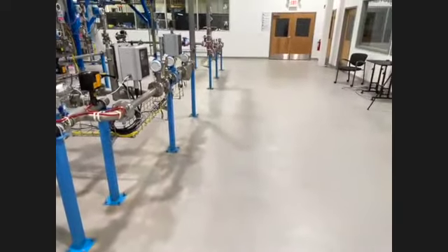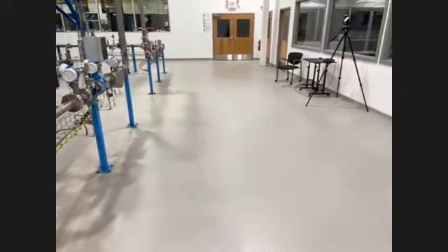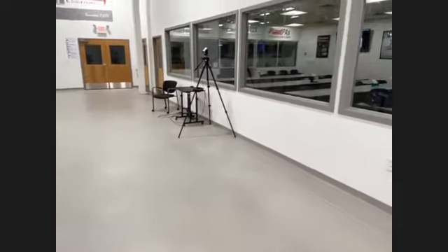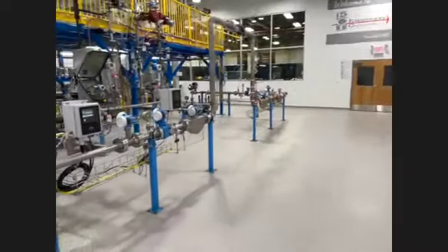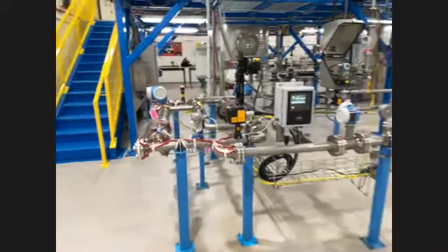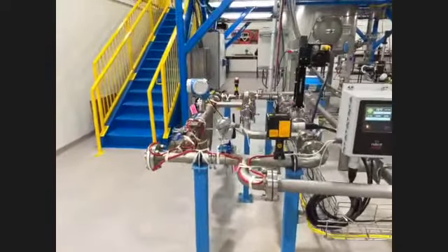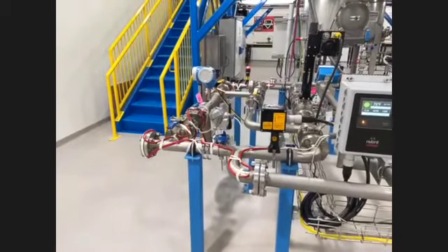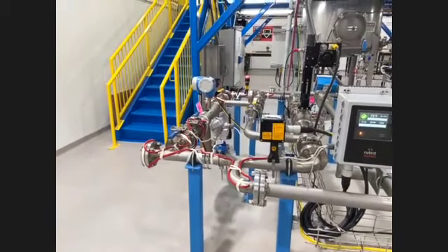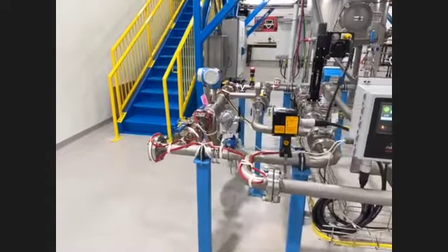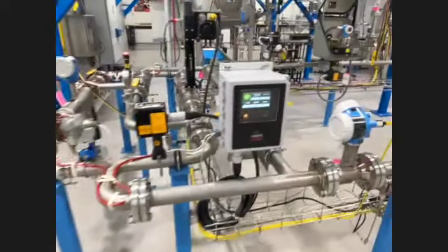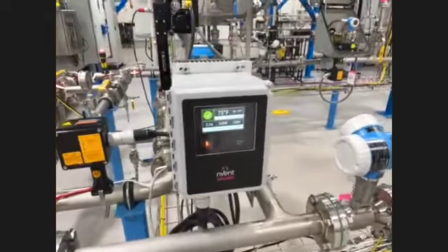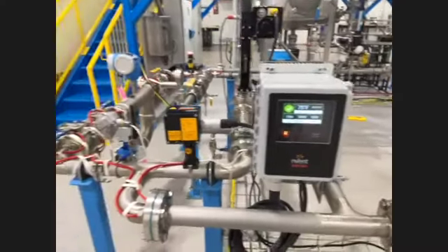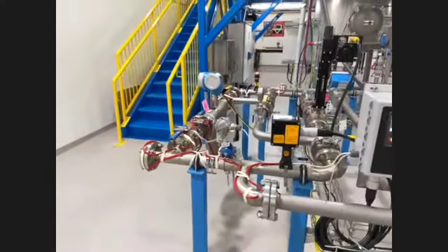And we also highly recommend isometric drawings. Very often the heat trace isometric drawing is something that is overlooked and is not deemed very important, when really, once this heat tracing is in and it's insulated, no one's going to remember what's going on underneath there. And if there is a problem, these digital controllers like you see here are great and really help point you in the right direction, but you don't really know what's going on underneath there without any record.